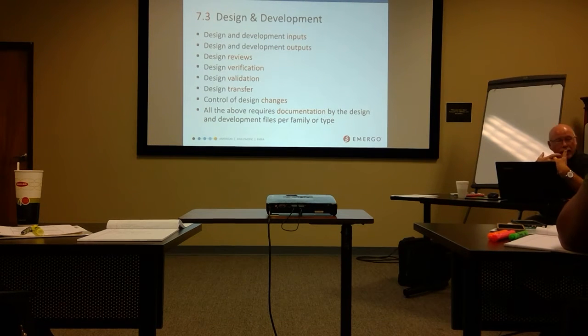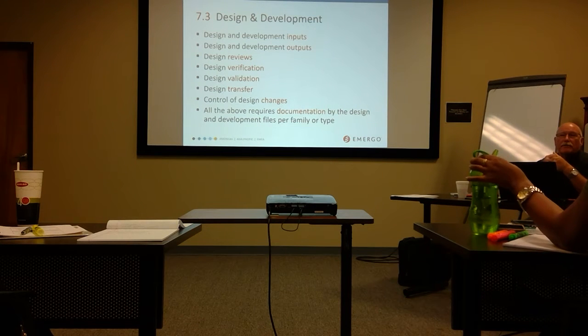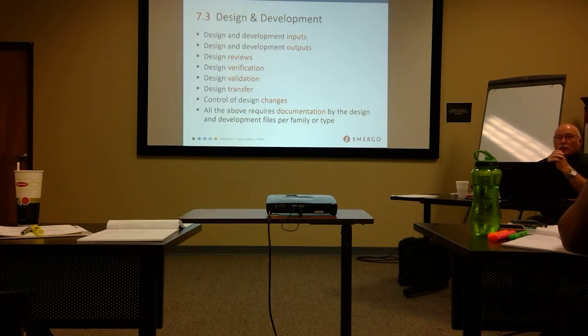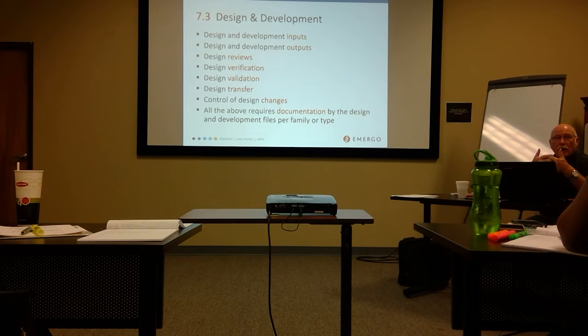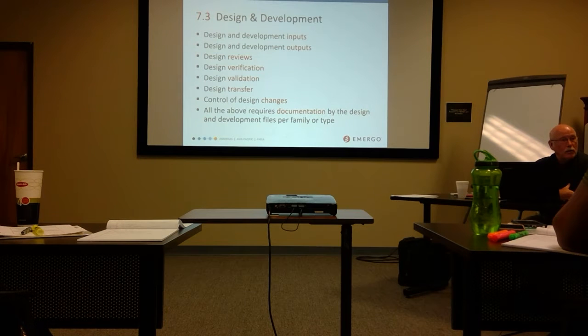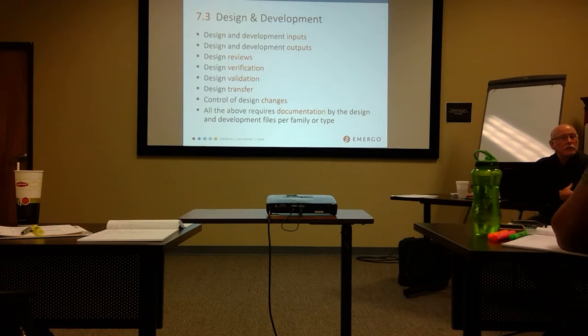So — inputs, outputs. If you submit, and you said you're class one so you're not submitting to FDA currently, but the first class two device you do where you have to submit a 510(k), this has to be submitted to the agency. They read this stuff in considerable detail. If you do not have this input-output matrix done and done well, you're going to get it kicked back with lots and lots of questions, which slows down the whole process. Better to build it in up front. Make sure you don't have any inputs that don't have corresponding outputs — that means you forgot to do the electrical safety testing. You should not have any outputs that don't have corresponding inputs. These things need to match one another.